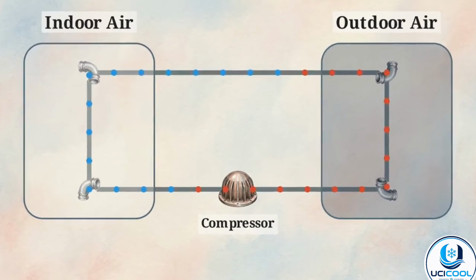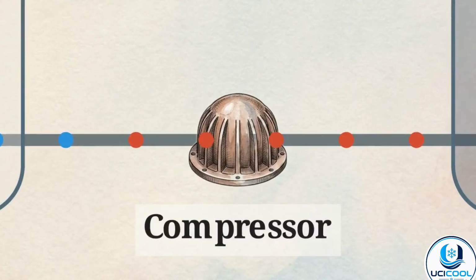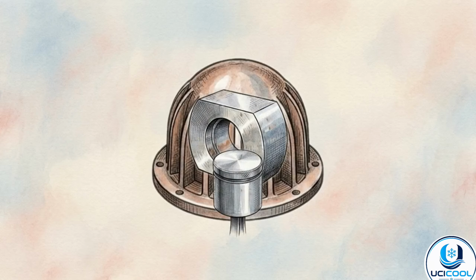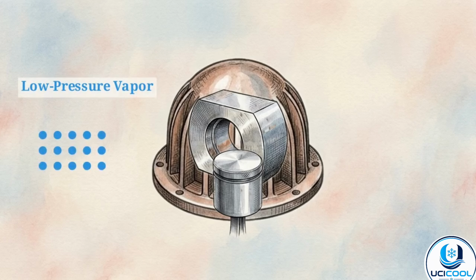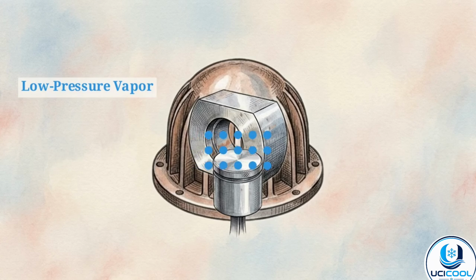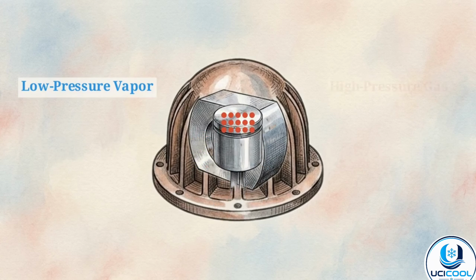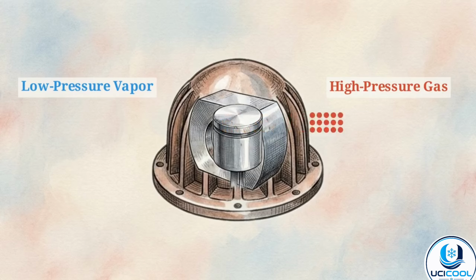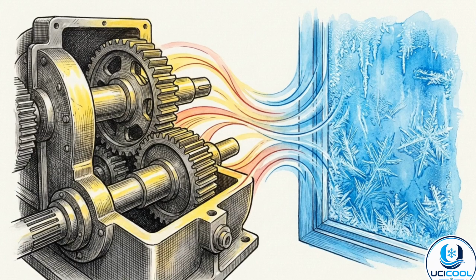This fluid acts as a vehicle, absorbing heat from the indoor air, carrying it through the system, and releasing it outside. For the refrigerant to move and dump that heat, it needs a driving force. This is the compressor. It takes in low-pressure, low-temperature vapor and compresses it, increasing pressure and temperature, turning it into a high-density gas capable of discharging heat. By manipulating these physical properties, the compressor provides the mechanical effort required to artificially lower the temperature of a space.